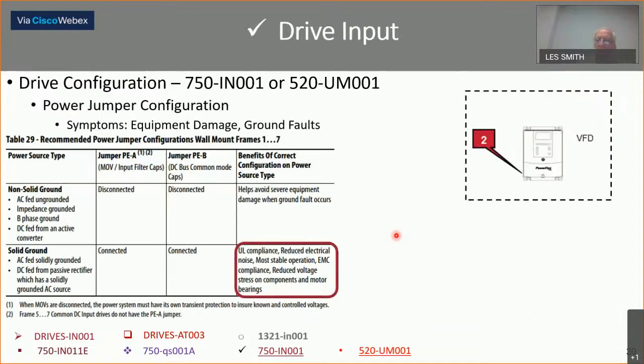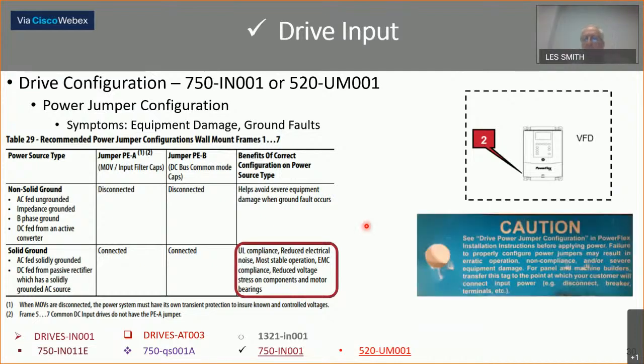And again, here's the statement off of this document here. It makes the statement: UL compliance, reduced electrical noise, most stable operation, EMC compliance, reduced voltage stress on components and motor bearings. And we'll talk about that next week. Oh, here you go. Here is the nameplate, or this sticker that comes on every 750 drive. Do you see that out there? That should be stuck somewhere around the drive, but this asks you to go read about the grounding system. That's on every architectural drive that's shipped.